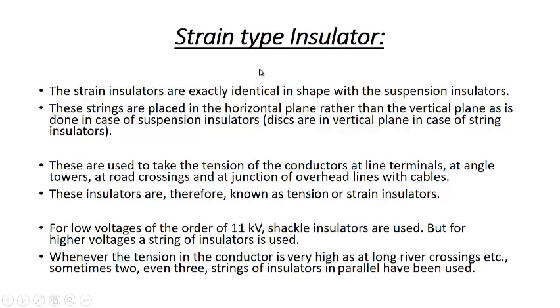Now coming to the strain type insulator. The strain insulators are exactly identical in shape with the suspension insulator. They are actually the same type of insulator. The only thing is that they should have more mechanical strength or tensile strength as compared to the suspension insulator. These strings are placed in the horizontal plane rather than the vertical plane, as is done in case of suspension insulators.